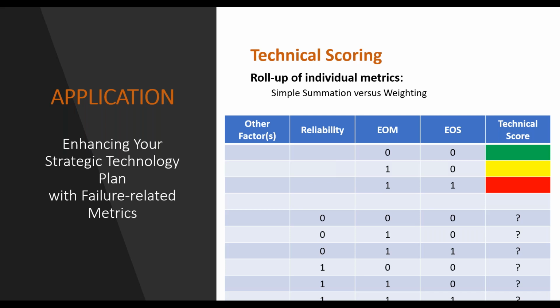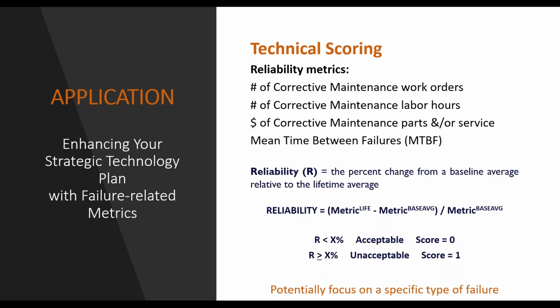The other way we've tackled it more recently is to use the end of life measures and age, doing the same sort of acceptable range thing with age as a life marker, almost like a reliability algorithm or calculation, where we look at the actual age of the device compared to its estimated useful life as defined by whatever source we're using.